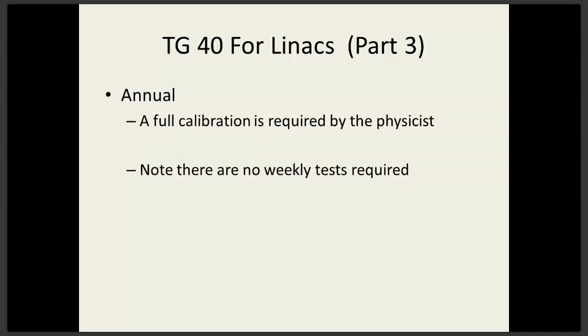And annually, the physicist does a full calibration. That's a total shakedown of the machine, almost like a mini commissioning every year, with a full report that is available for state regulators to inspect and also for the American College of Radiology or ASTRO or ACRO to inspect. There has to be a full annual calibration by the physicist every year, or your department will not get accredited.